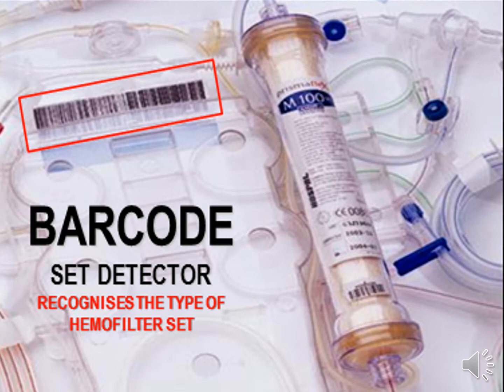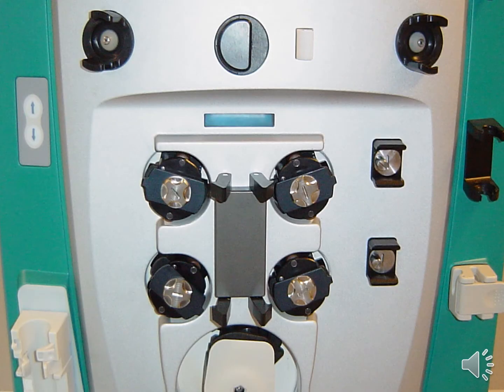Then you've got the barcode set detector, and its function is a safety feature that recognises the type of filter set that you're going to employ, so that you use the right therapy in the setup and the right filter for the therapy that you're going to initiate. Here is the machine, and once you put the cartridge in, this is where it senses the barcode. It either passes or fails.